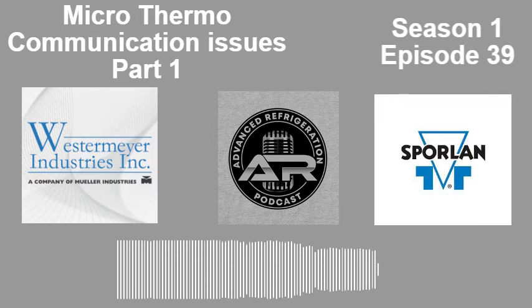And what that does, Brett gave a great description, this looks back to the HMI. The HMI looks to this and says, oh, you're the alarm node. And boom, without you having to type anything in, everything that needs to be uploaded to this alarm node is done for you automatically. Now, yes, Brett is correct, if you choose, you could type in the alphanumeric, because every chip has its own individual, unique identifier. But for me, I'll fat finger it. I'll never trust myself, so I always use the service pin.